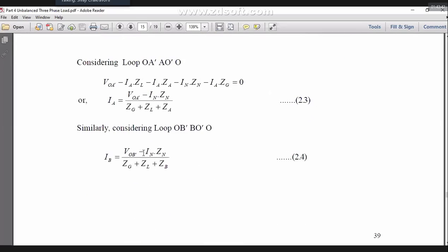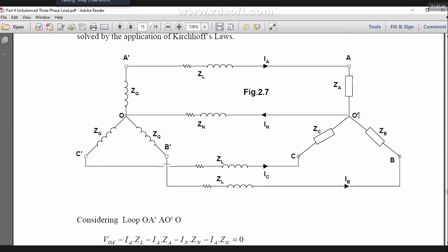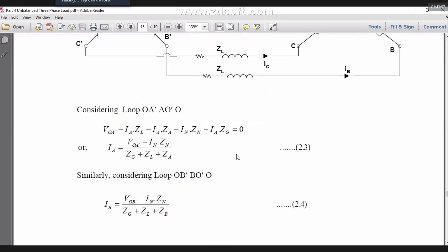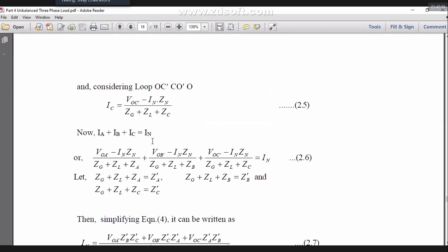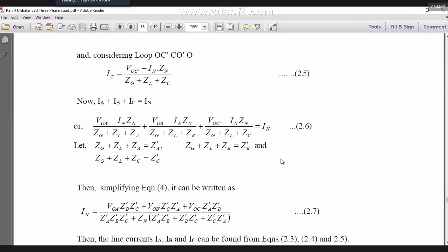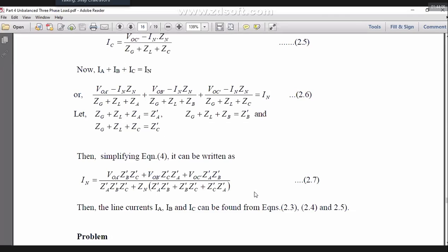That's the big problem. So these are all neutral here. So it's a four-wire star. By the way, please remember, if it is a four-wire system, it cannot be delta. It has to be star. Delta is always a three-wire system. So it's a four-wire star with a neutral impedance. And the problem is, in the neutral, we always have a different impedance. Why? Because the neutral wire configuration is different from the line wires. First of all, the dimension is not the same, etc.